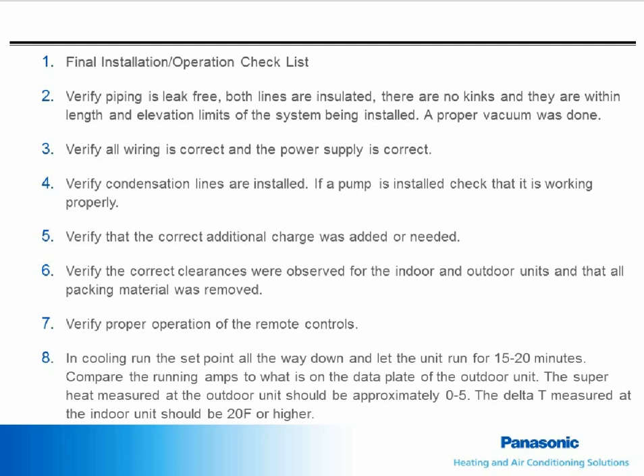In the cooling mode, set the temperature as low as it will go and let the system run for about 15 minutes. Measure the running amps and compare it to what is on the data sticker. Check the superheat at the outdoor unit. Measure the temperature of the suction line within a few inches of the flare connection and write it down. Take a pressure reading at the suction line service valve and convert it to temperature by using the conversion chart on your service gauges. Subtract the converted temperature from the temperature on your thermometer. This is your superheat. If the compressor is ramped up, the unit is properly charged, and there are no airflow or line set restrictions, the superheat should be around 0 to 5 degrees Fahrenheit.